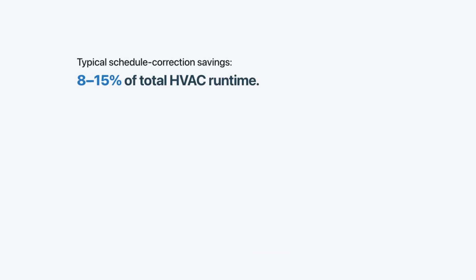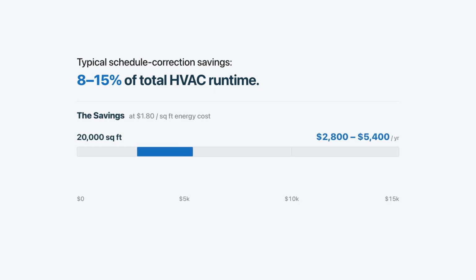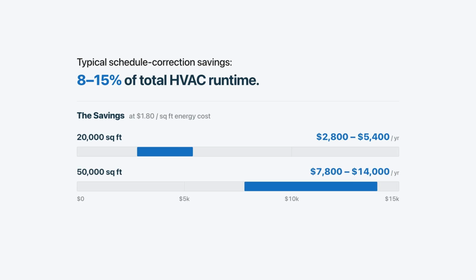Research from PNNL and field measurements consistently show schedule corrections alone saving 8 to 15% of the HVAC runtime in buildings where the schedule has drifted. For a 20,000 square foot building with typical energy costs, that's roughly $2,800 to $5,400 a year. For a 50,000 square foot school, $7,000 to $14,000 a year.